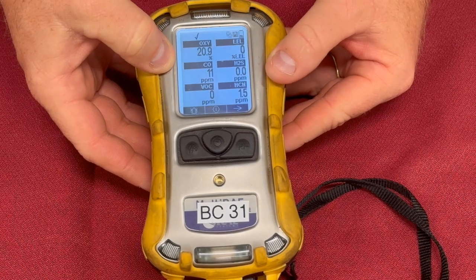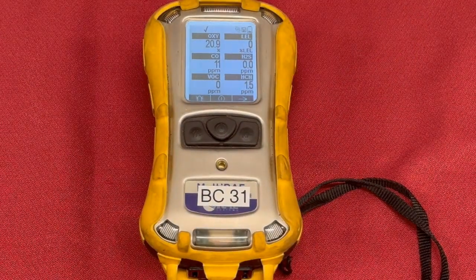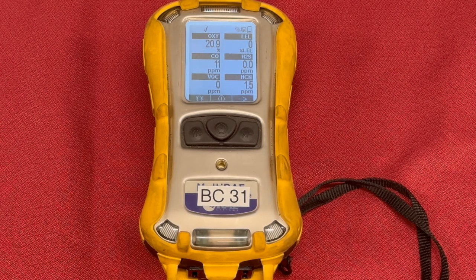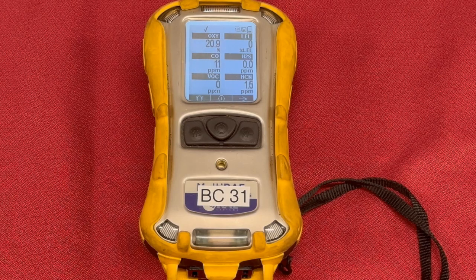Next one down here is CO. That's carbon monoxide, a byproduct of combustion. Our sensor's set to go off at 35 parts per million. Well, that's a relatively low number in comparison to an environment where there's a big CO leak. The reason we've set it so low is because, one, that's the NIOSH standard, and then also it allows you time to put an air pack on.